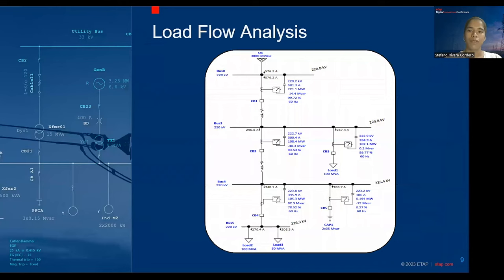After the adjustment process, it was achieved that the load flow of the virtual model had a deviation of less than 1.5% with respect to the real flow, which we consider low enough to be able to carry out the short circuit simulation and compare its result with those of the real short circuit.